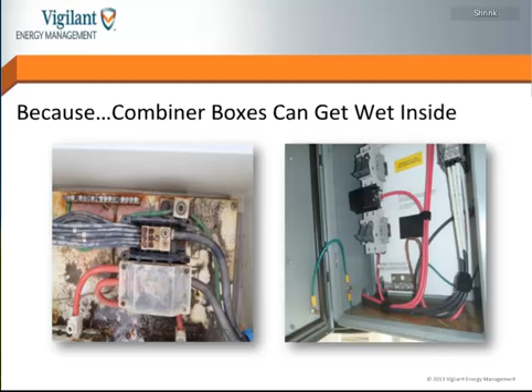You can see in these 2 pictures, it's quite a bit of water that can build up in these combiner boxes just from condensation. And in this first picture to the left, you can see all the corrosion and slop in there. This wasn't one of the systems that we installed, but we inherited the site and we're maintaining it. And we opened one of these boxes and found actually more water than what's shown here. And the high water caused a ground fault and the system shut down. So that's what triggered us to go out there and do the service call. So this shouldn't happen. These conduit openings should be sealed. And don't use duct seal. That is not rated for outdoor. You should use something like Heyco cord grips, or some kind of a cord grip that's made for these systems, or even expanding foam. Not the Home Depot kind out of a can, but expanding foam that's really made for the purpose. The Home Depot stuff will work, but it's not made for the purpose.